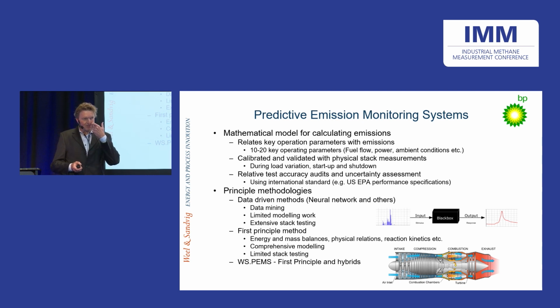On the other hand, there's the first principle method, where instead of relying on implicit relations, we use energy and mass balances to calculate what's happening in the combustion zones, then apply reaction equations to precisely calculate the concentration in the stack. We still use stack testing to validate and calibrate the model, but with the first principle model we can significantly limit the amount of stack testing needed, which is very important for remote sites and offshore applications.